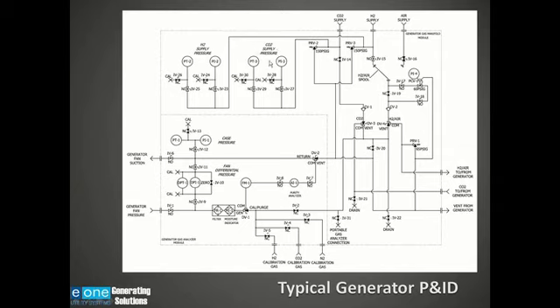So here we have the CO2 supply pressure coming in. There is a pressure relief valve so that it doesn't build up too much pressure. We have a local pressure indicator that tells what our CO2 supply pressure is. We also have a transmitter that's measuring the CO2 pressure. That will feed a signal back to the control room so the control room knows what the CO2 pressure is. And note the calibration ports on these, because this becomes important when you are establishing calibration procedures for your equipment. Being able to calibrate the equipment without having to disconnect components or take the unit offline.